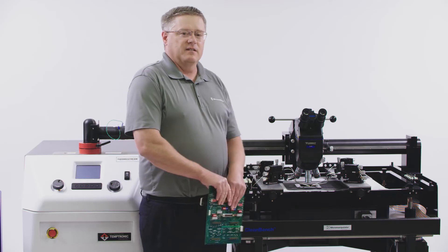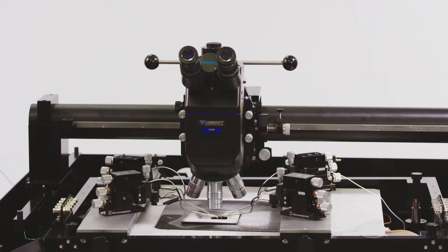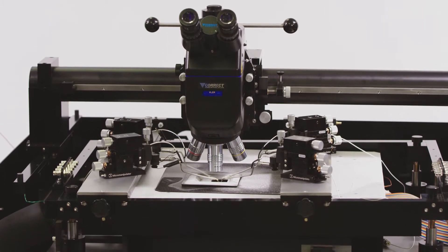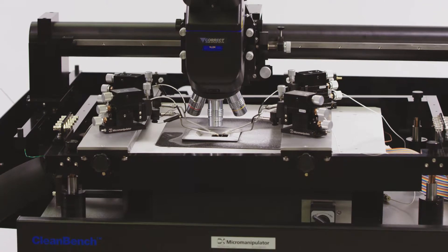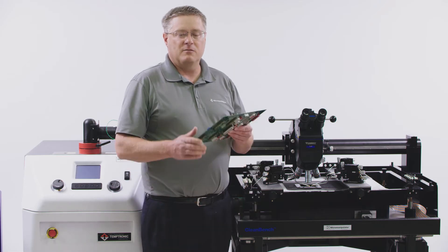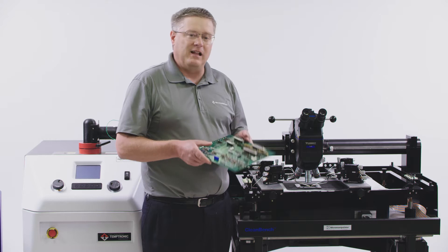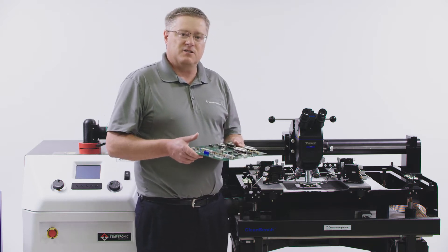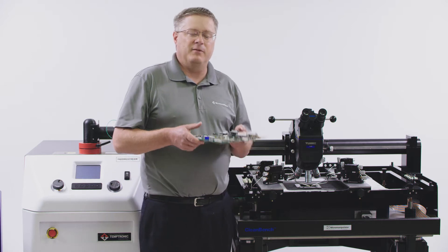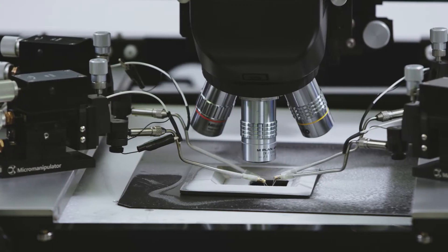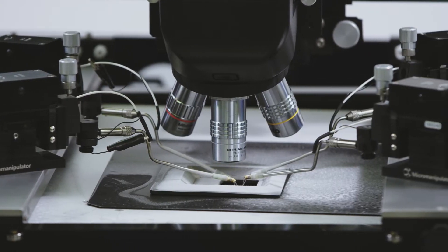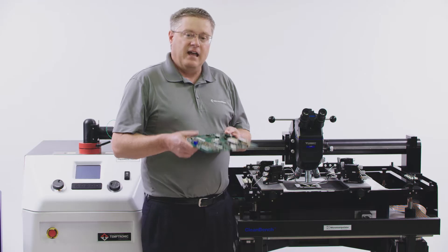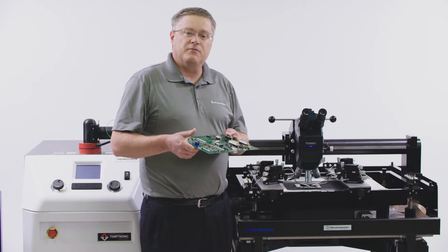You can now test board mounted devices at temperature with the Versa system. This Versa is configured for temperature testing for minus 40C to 125C of board mounted devices. Whether your devices are mounted onto an application board, development board, whatever it is that you're mounting your boards to to exercise them for your FA, your product development, your product test needs.